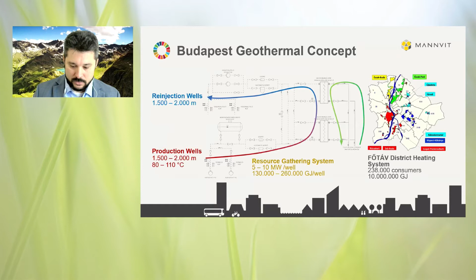The lowest temperatures could be directly used. Cold water can be used for cooling - a very obvious or evident solution, but still rarely used, maybe because of the very thin window of temperature, 5 to 15 degrees Celsius, where it could be used directly for cooling. But that's a very efficient solution, and could be used more than it is today.